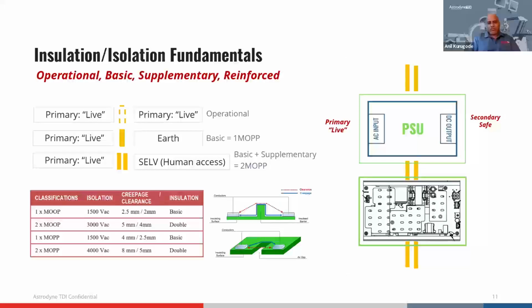It's important to know that none of this is negotiable for a certain class of equipment, as we've seen before. For class 1, these levels will be a little lower, but for class 2, because there's a missing earth and the human becomes the earth, the levels of test are much higher. So fundamentally, wherever a person is involved, this 2 MOP, or two means of protection, is needed.